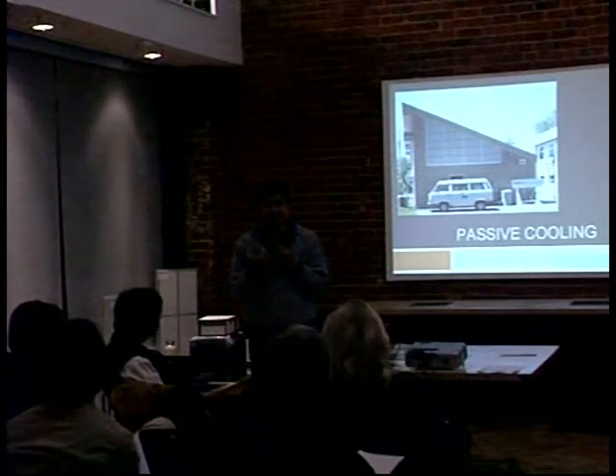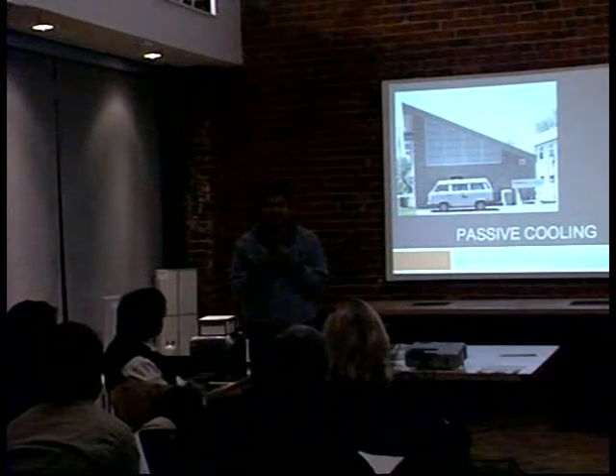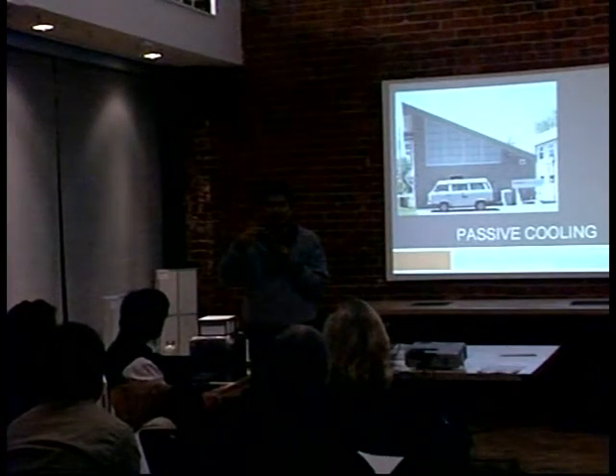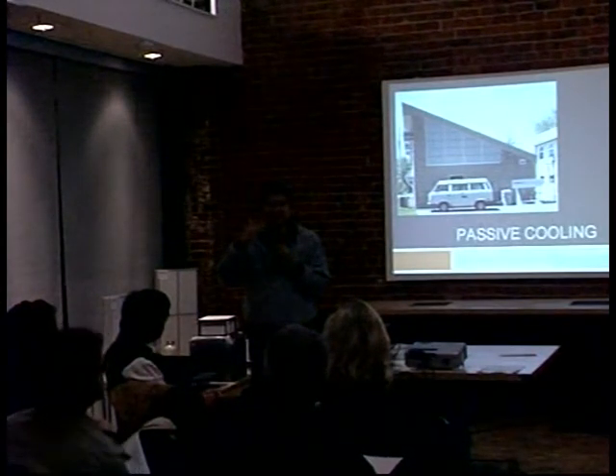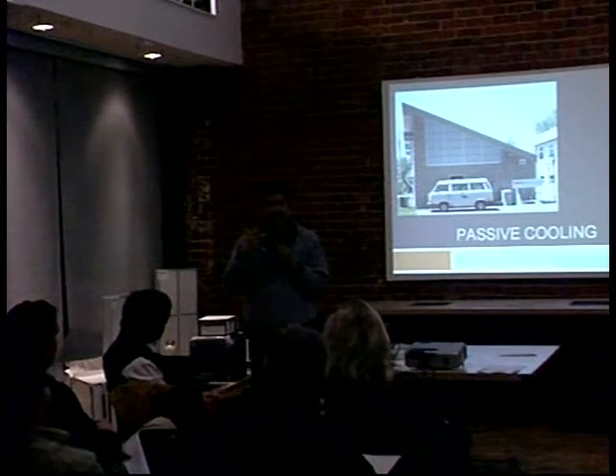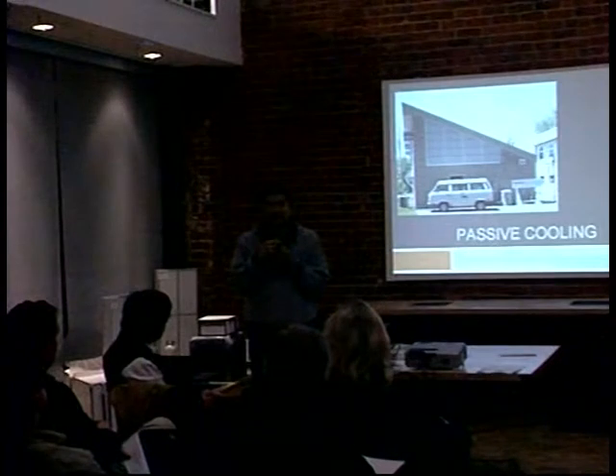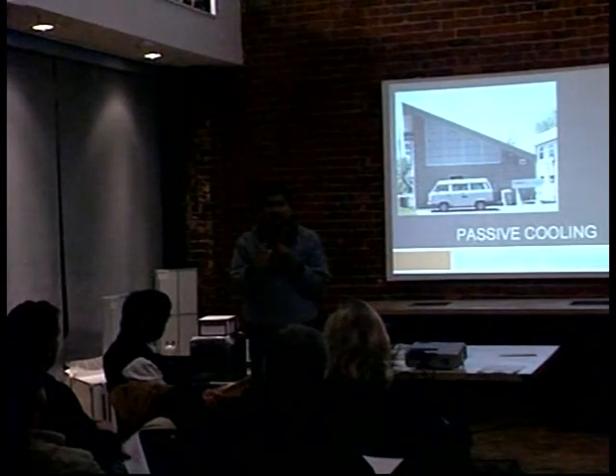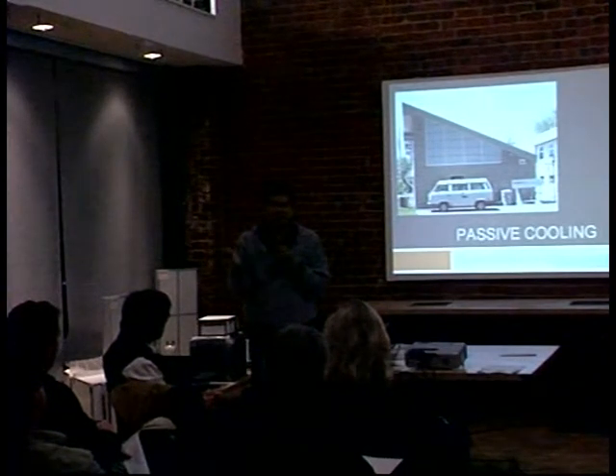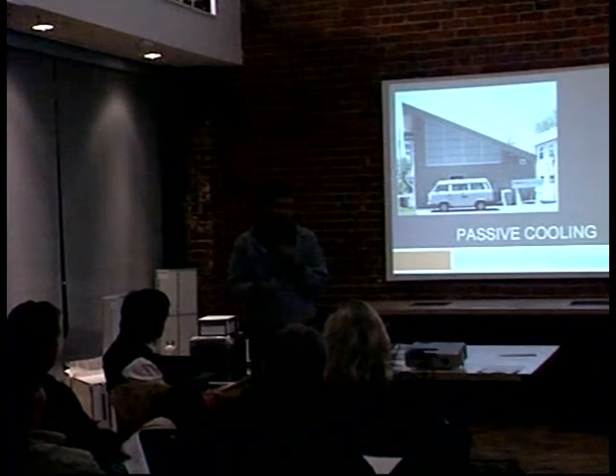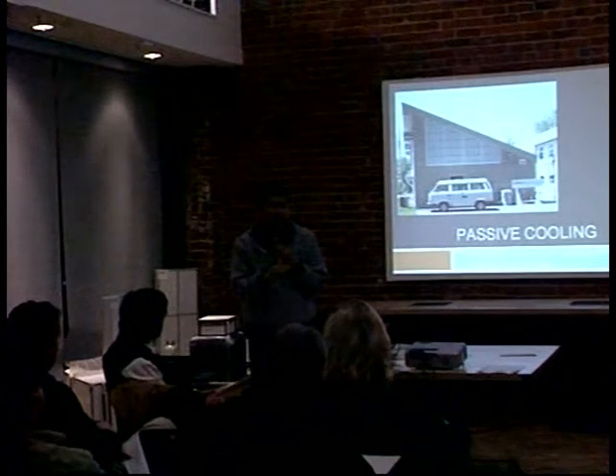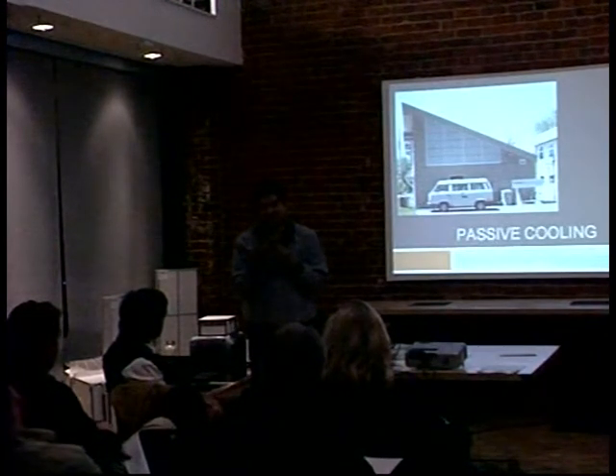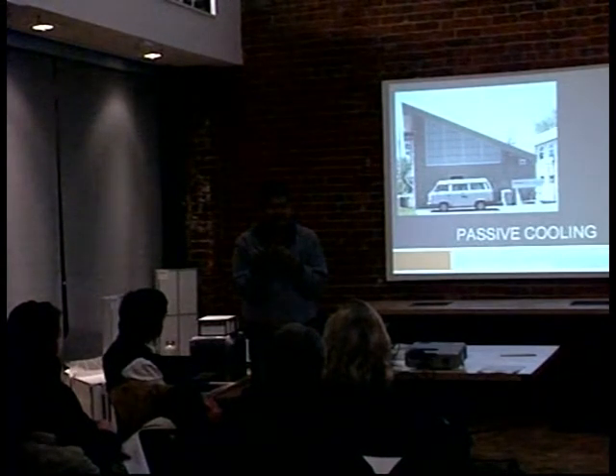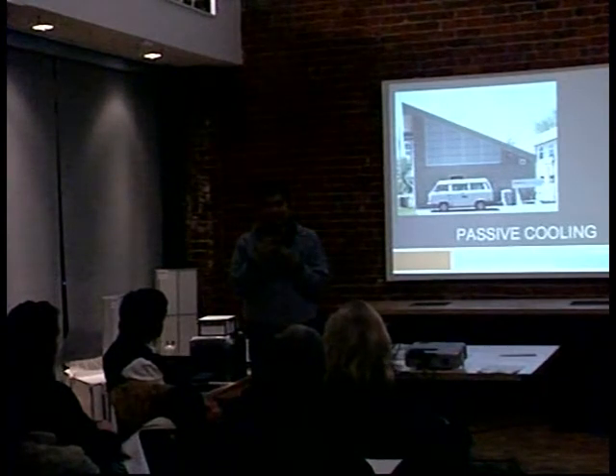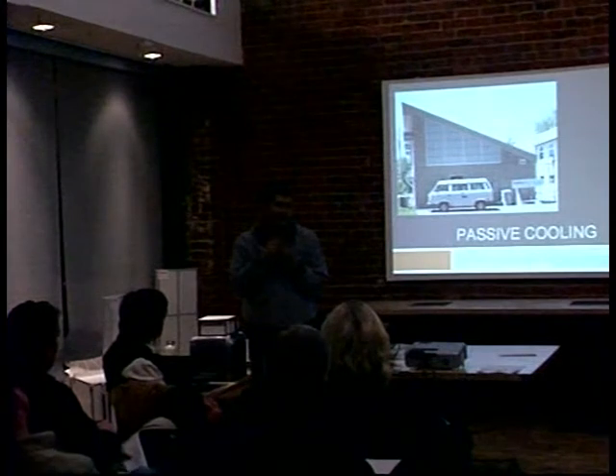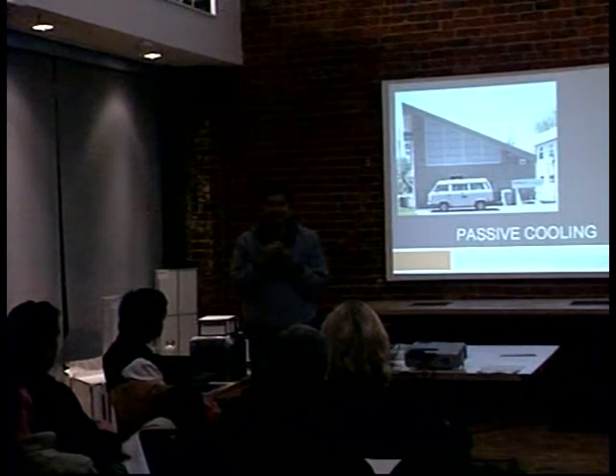But in general, it can be - though of course we have to consider the increase in fan energy required. If we provide night flush by using fans, that's huge compared to the standard ventilation rate - let's say for office buildings or hospitals, even 2 air changes per hour for normal fresh air operation, compared to night flush which can be as high as 10 to 20 ACH. If you want to cover that with fans, the increase in fan energy will diminish whatever savings you have.